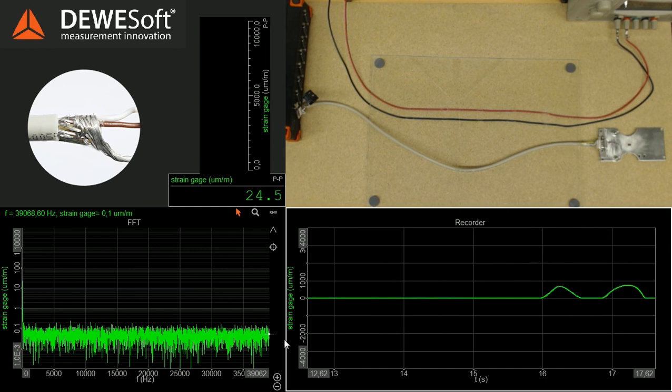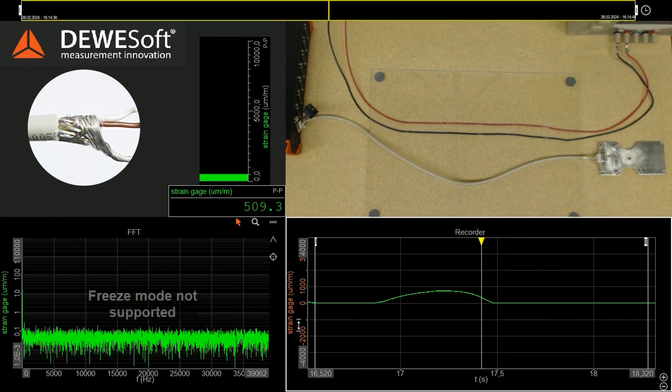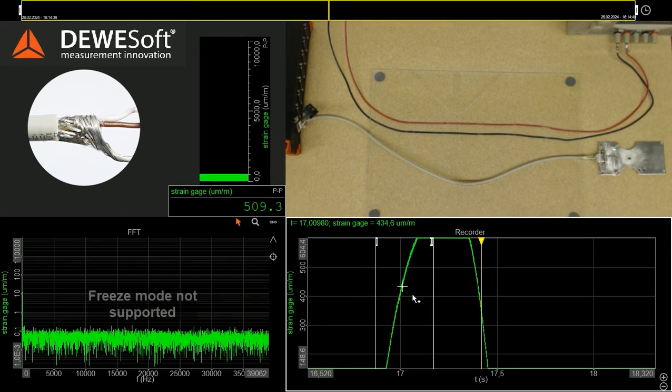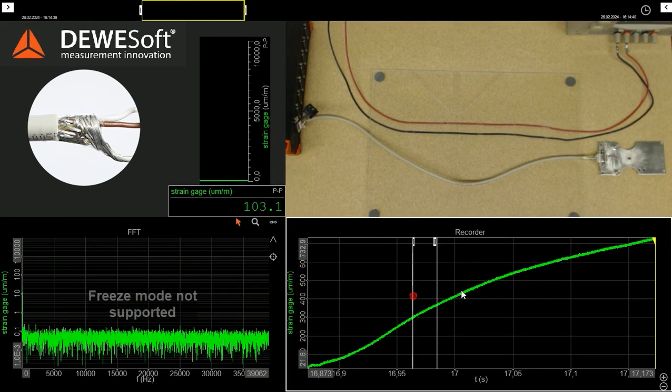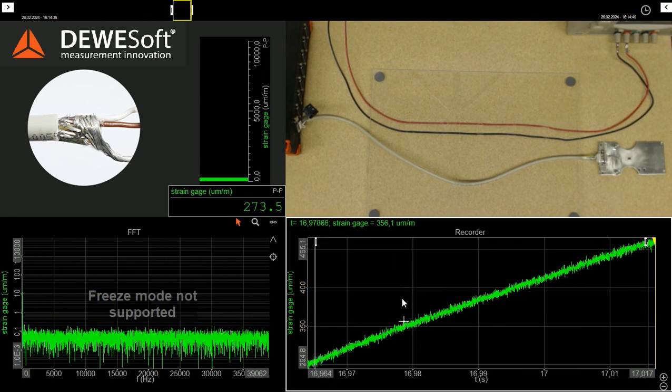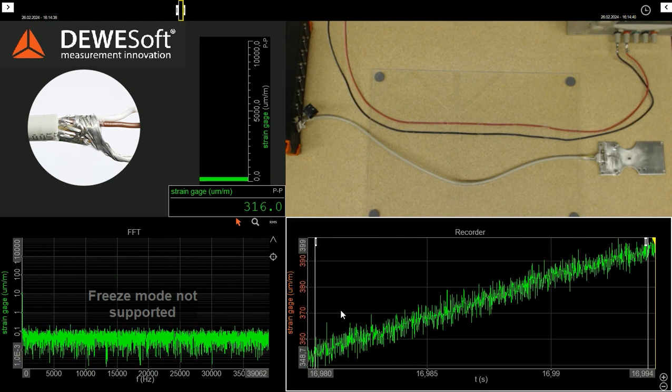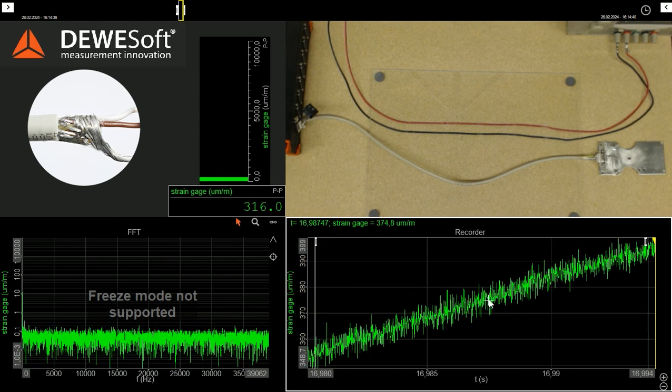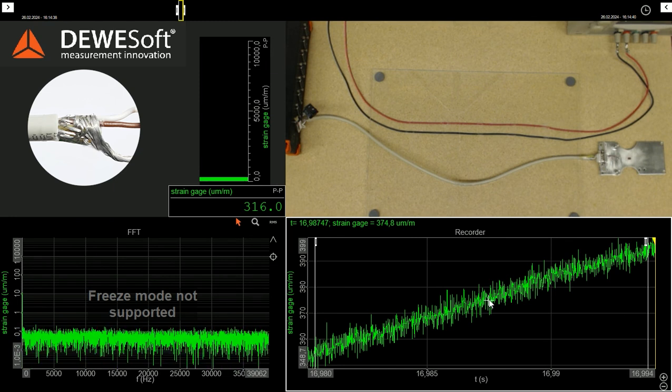So the sensor signal looks useful and nice now. But is it good enough? Let's zoom in. There's still a small noise of around 10 µm per meter peak peak on it.